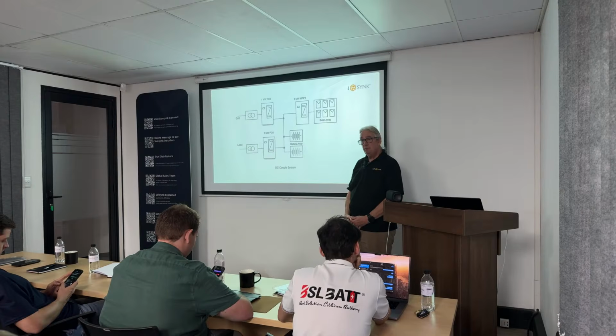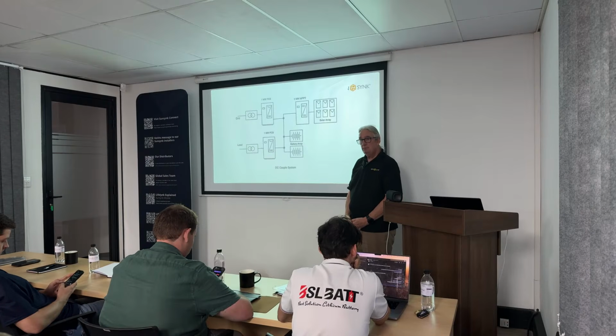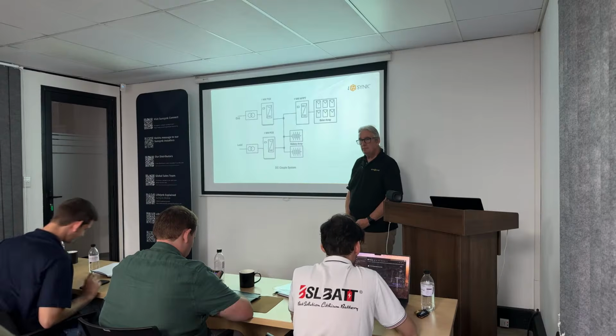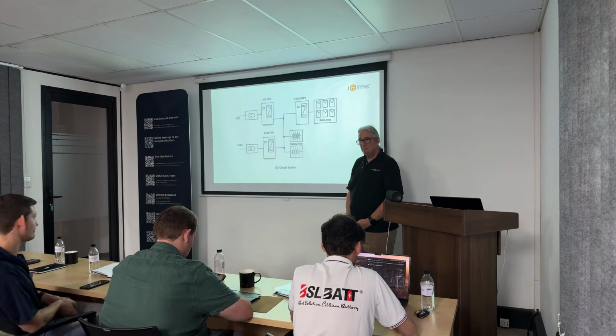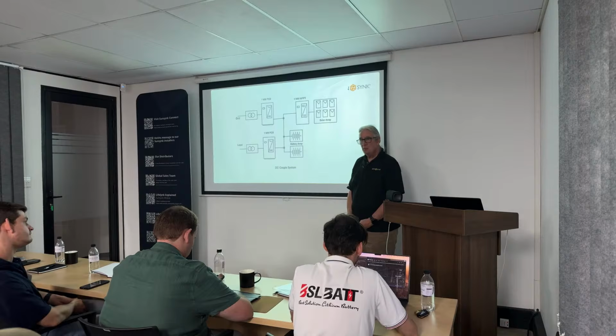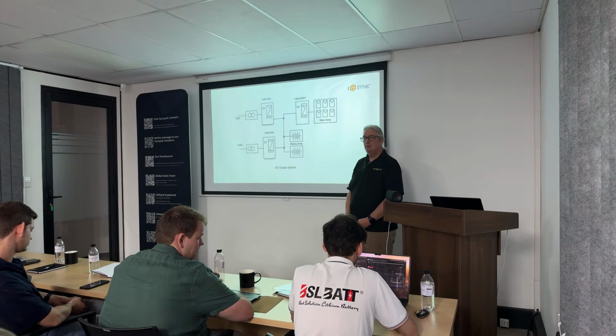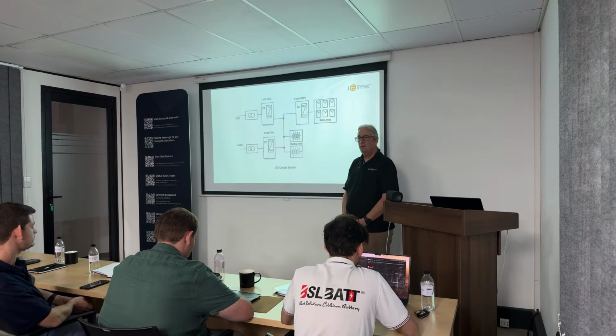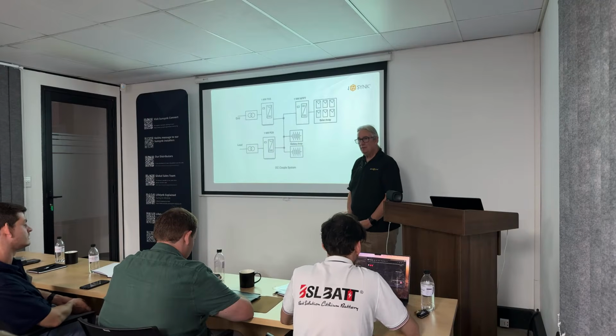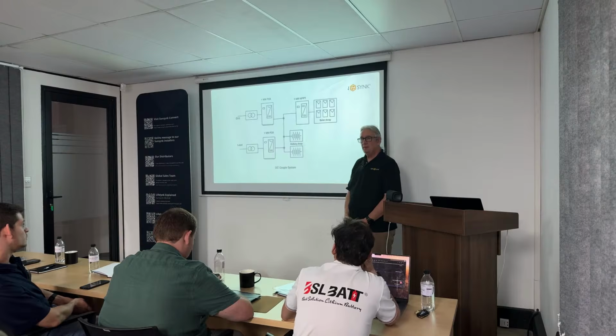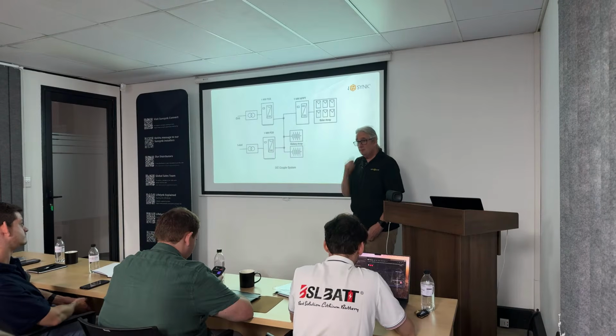The reason I ask is we have what we call a small scale embedded generation application that you have to put in with your municipality. Typically, if you've got a grid-tied inverter and a battery inverter, they look at your capacity by adding the two together, the battery and the grid-tied, as your combined generating capacity of the facility. And it can't be more than 70% of your nominated maximum demand.